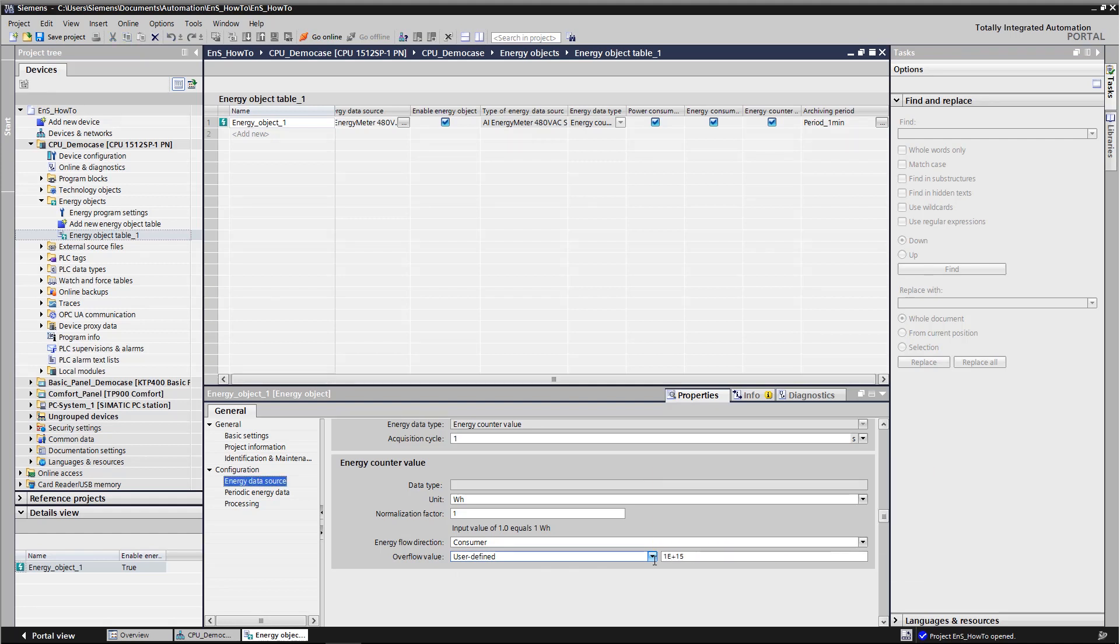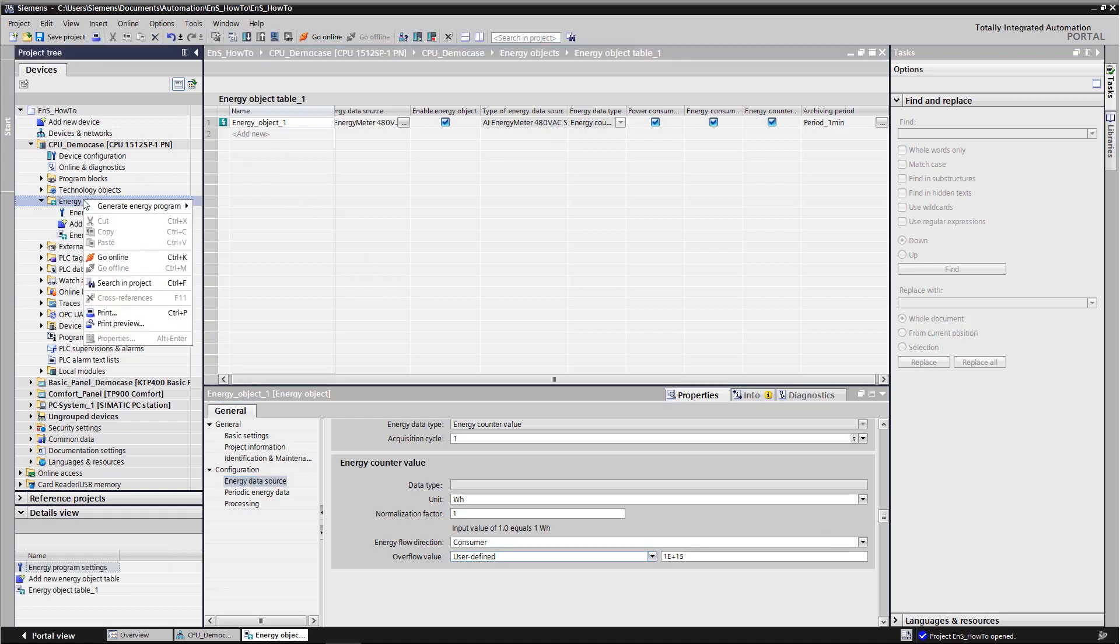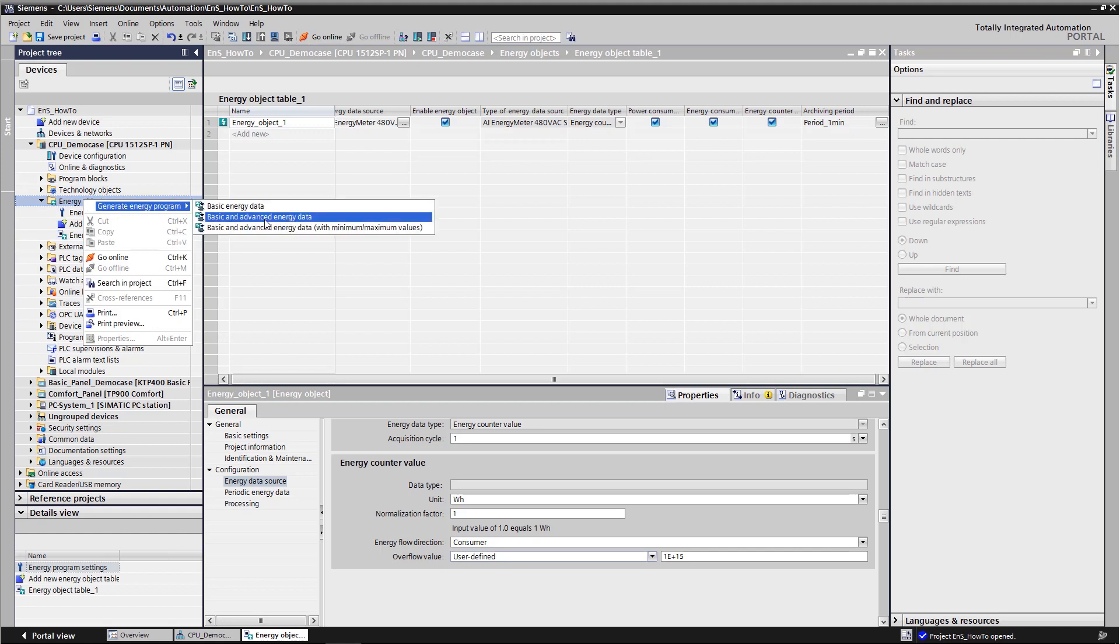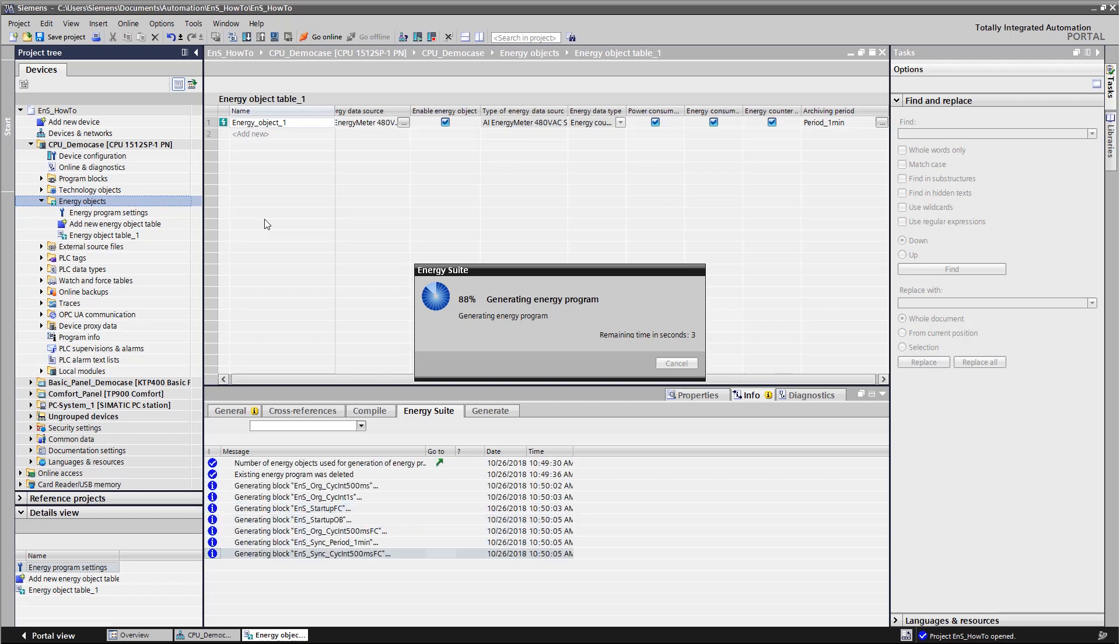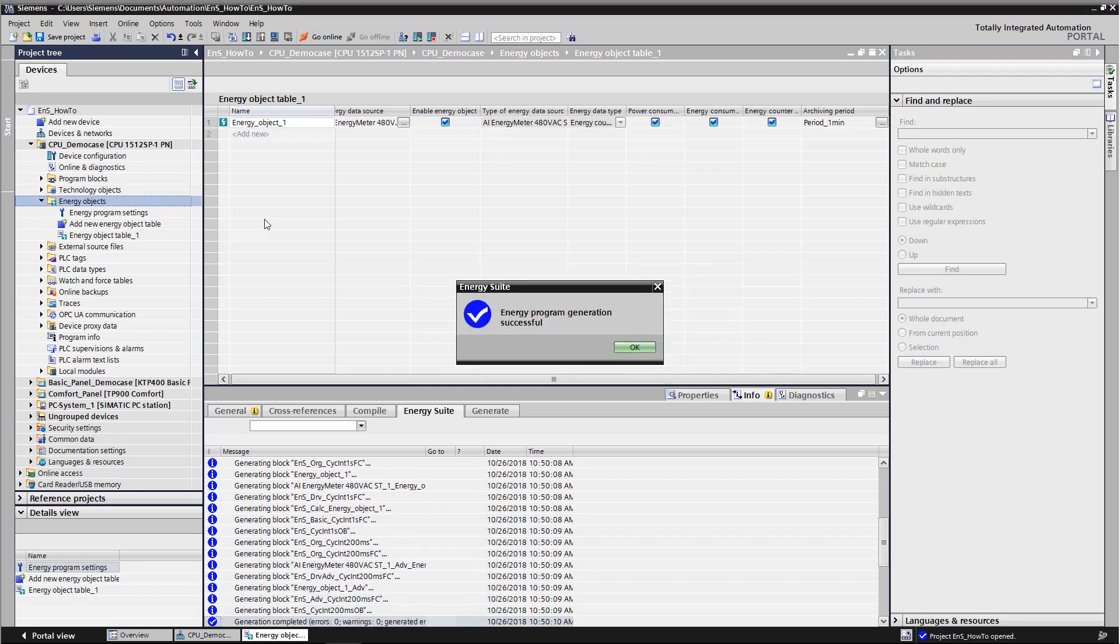Now we can generate the PLC program. As the energy meter is one of the measuring instruments supported by energy suite via a special driver library, we are able to generate advanced energy data. That means we not only receive data that is relevant for invoicing, such as average power, but also additional data such as individual voltages, currents, or power factors.